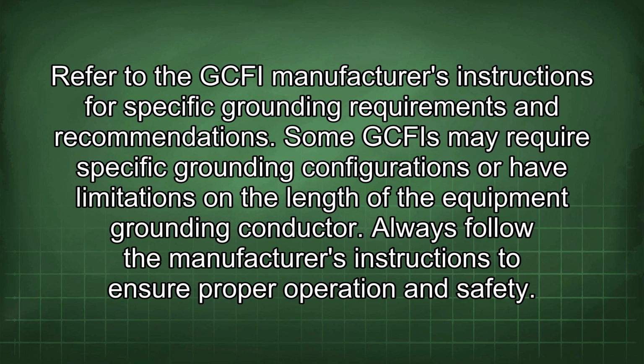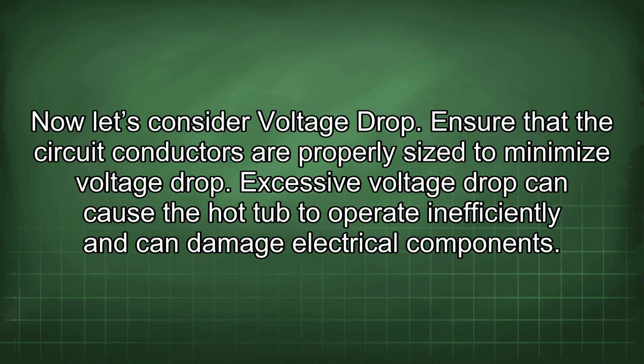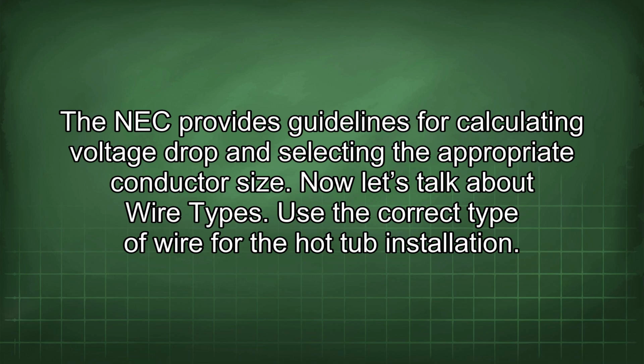Always follow the manufacturer's instructions to ensure proper operation and safety. Now let's consider voltage drop. Ensure that the circuit conductors are properly sized to minimize voltage drop. Excessive voltage drop can cause the hot tub to operate inefficiently and can damage electrical components. The NEC provides guidelines for calculating voltage drop and selecting the appropriate conductor size.